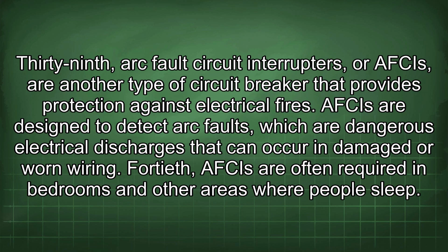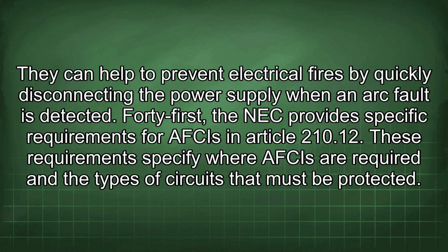39th, arc fault circuit interrupters, or AFCIs, are another type of circuit breaker that provides protection against electrical fires. AFCIs are designed to detect arc faults, which are dangerous electrical discharges that can occur in damaged or worn wiring. 40th, AFCIs are often required in bedrooms and other areas where people sleep. They can help to prevent electrical fires by quickly disconnecting the power supply when an arc fault is detected. 41st, the NEC provides specific requirements for AFCIs in Article 210.12. These requirements specify where AFCIs are required and the types of circuits that must be protected.